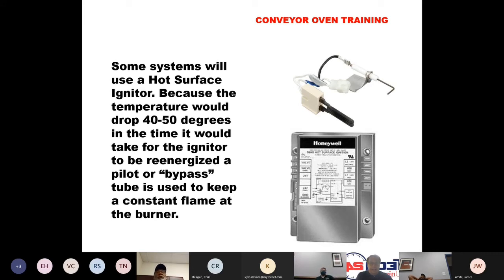I've never had much luck cleaning the sensors on these hot surface igniters. You can try to do that. The problem is they're very delicate. So it's always a good idea to have a new one with you before you try and pull this one out. You also, on a lot of the Lincolns, will have to pull your conveyor oven to get the burner to come all the way out.